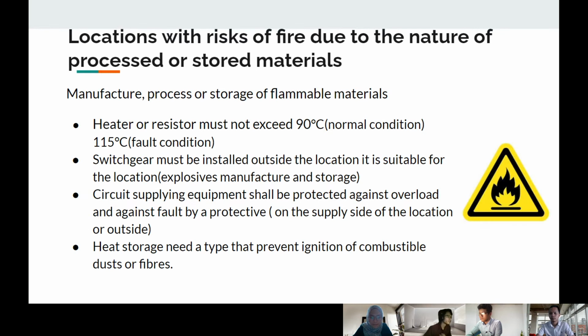Next, locations with risk of fire due to the nature of the process or stored materials. This slide is about storage of materials. For storage of materials, a heater or resistor must not exceed 90 degrees Celsius under normal condition, and 115 degrees Celsius for fault condition. The switchgear must be installed outside the location unless it is suitable for the location. This is for explosive manufacture and storage, where the switchgear must be put outside the location.